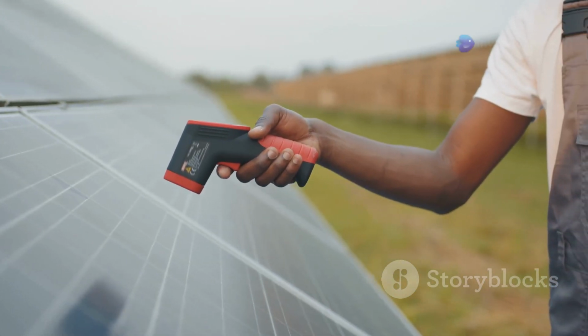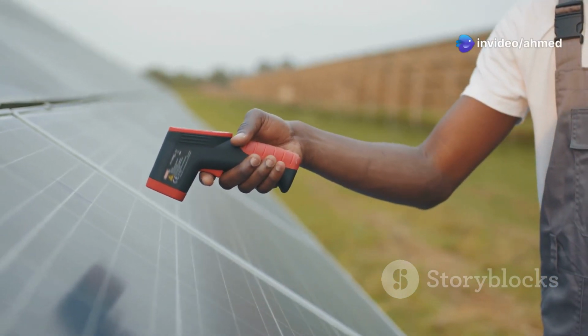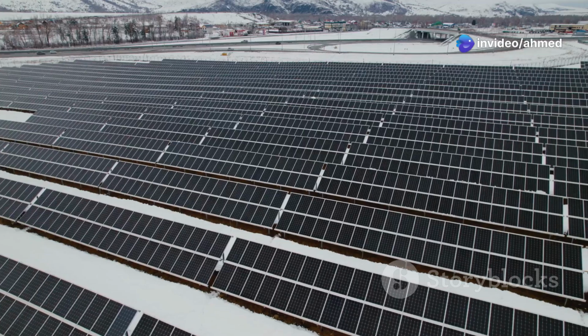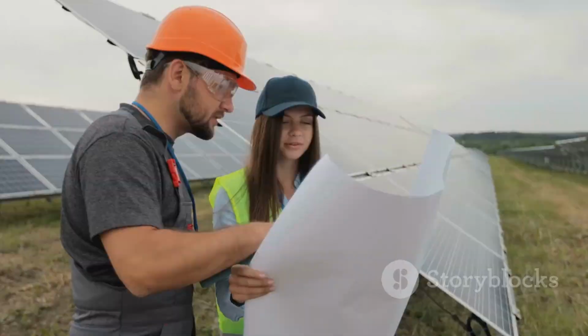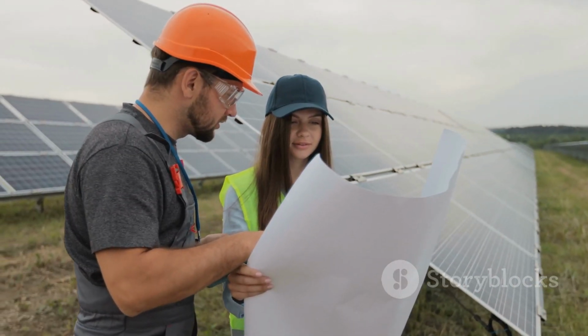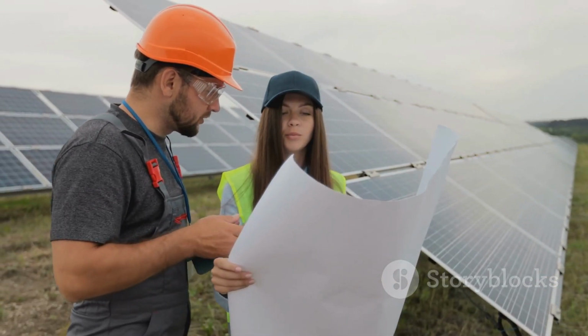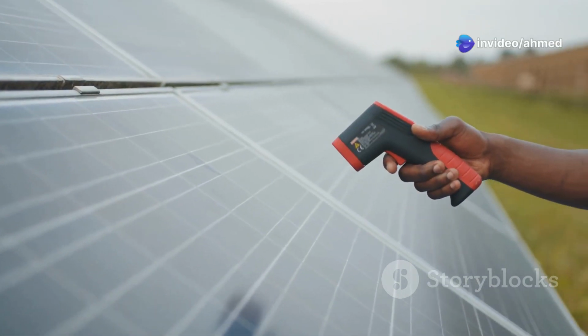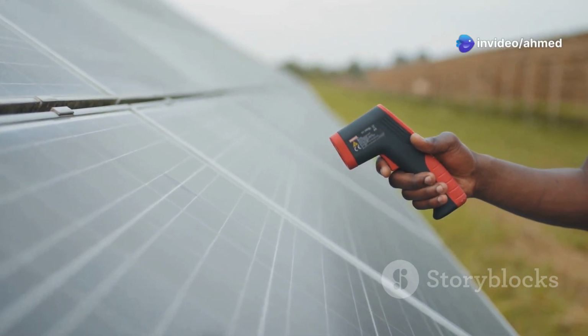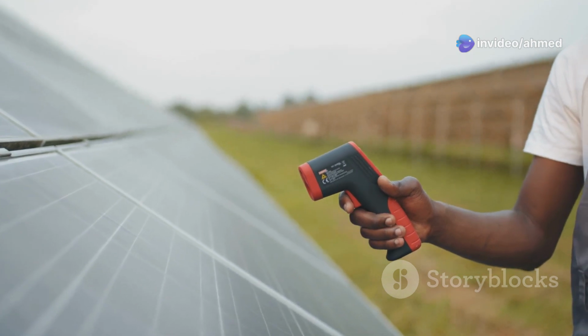Note: the voltage of PV modules has an inverse relationship with temperature. A module's voltage will increase in cold temperatures and decrease as it gets hotter. This relationship must be considered and calculated for proper string sizing. An IV curve for a typical PV module. Note that module voltage decreases as temperature increases, while the effect of temperature on module current is minimal.